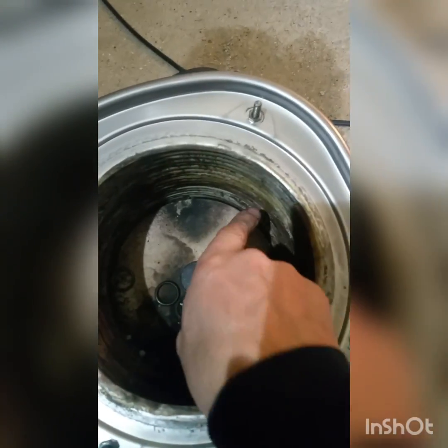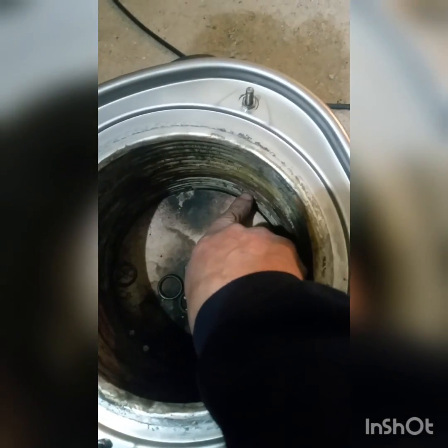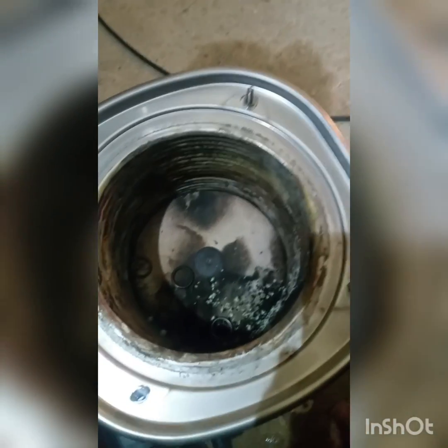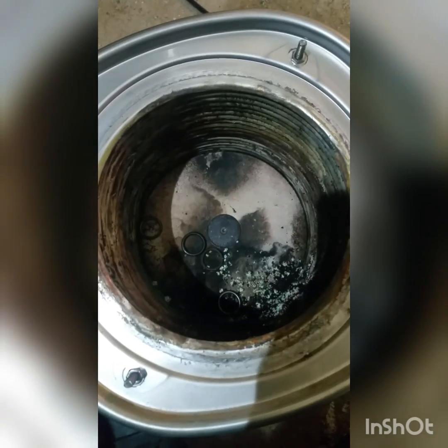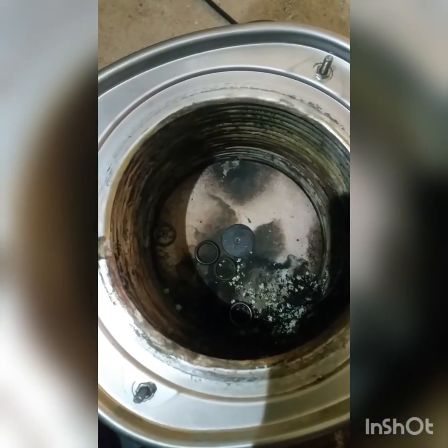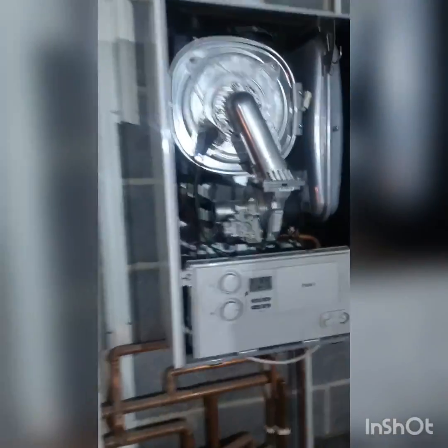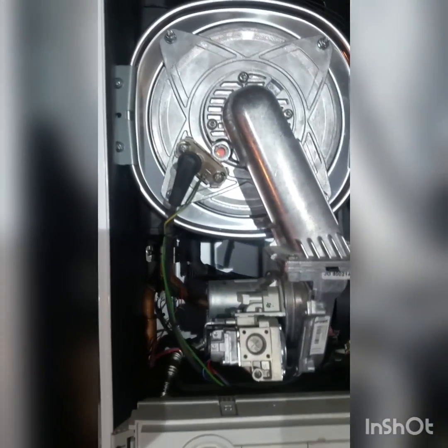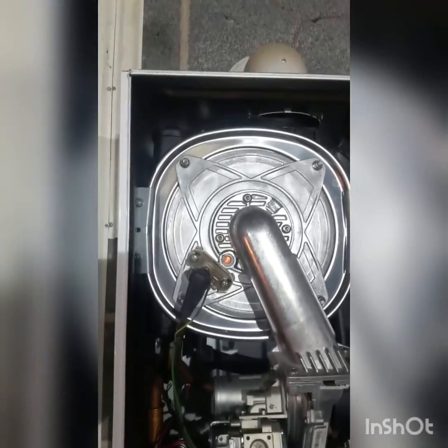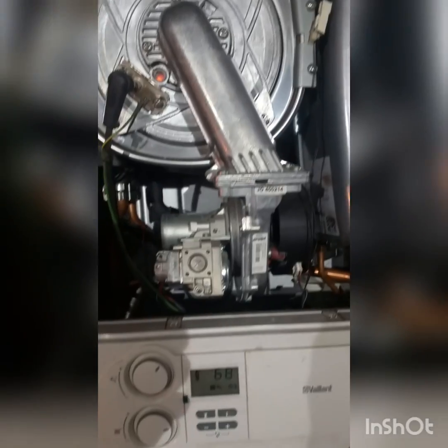Basically it's got a leak just up here. One of the pipes has burst there, or fractured or rotted away, or whatever. So got some resulting damage inside there. They're just O-rings where I've changed it. So popped a new heat exchanger in, literally just fired up. Got some tests to do on this boiler now, and ready to go.